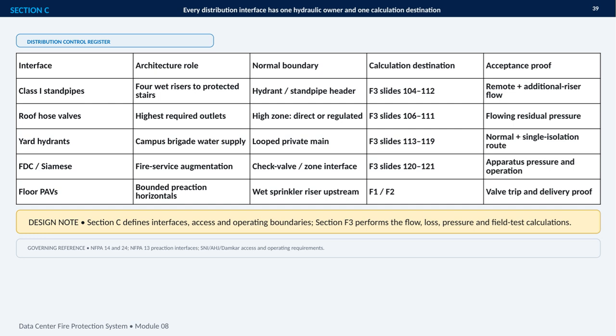Roof hose valves represent the highest required outlets, so the design must verify flowing residual pressure in the high zone. Yard hydrants support the campus brigade through a looped private main, with testing that includes both normal operation and a single isolation route. The FDC, or Siamese connection, is the fire service augmentation point, verified through apparatus pressure and operation. Finally, floor PAVs define bounded preaction horizontal systems, with valve trip and delivery proof assigned to F1 and F2.